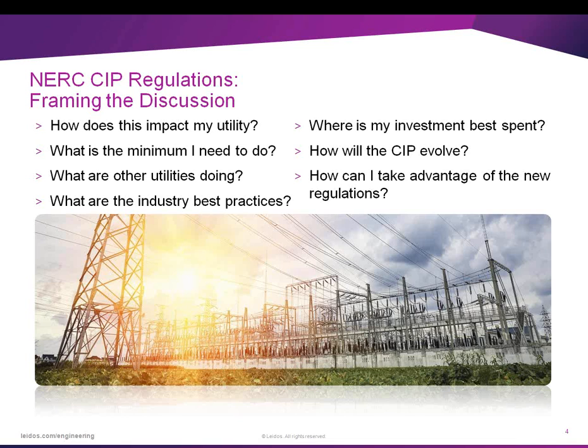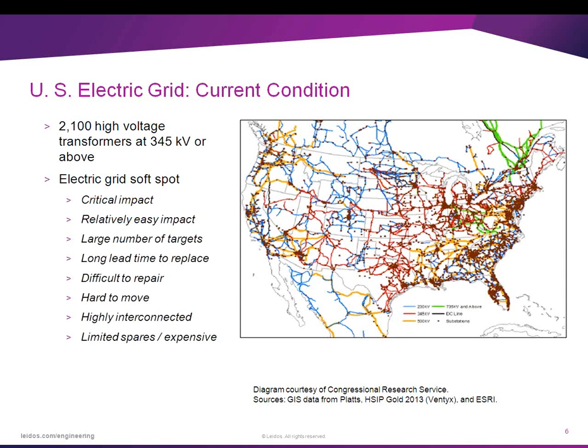Transformer replacement lead times are long, sometimes as much as 60 to 80 weeks, depending on the location of the manufacturer and the size and type of the transformer itself. On-site repair to damaged windings is a difficult proposition at best, and most probably impossible to accomplish in many instances. Transformers are very difficult to move, with significant logistics, planning, and permitting required to make that happen.